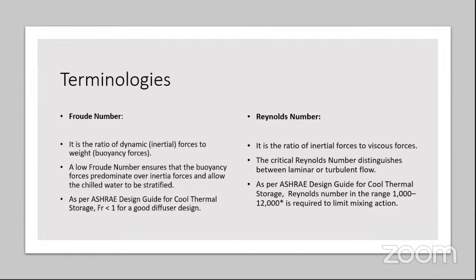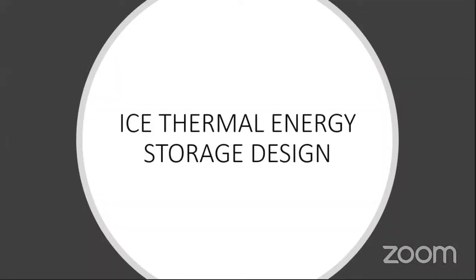Now, Reynolds number is the ratio of the inertia forces versus viscous forces. It has more to do with the boundary layer of the thermal storage tank, but it's an important parameter for the diffuser design as well. So as per ASHRAE design guide for cool thermal storage, Reynolds number should be in the range from 1,000 to 12,000, depending upon the mixing action affordable for achieving the desired stratification. So that was about the stratified thermal storage tank design.